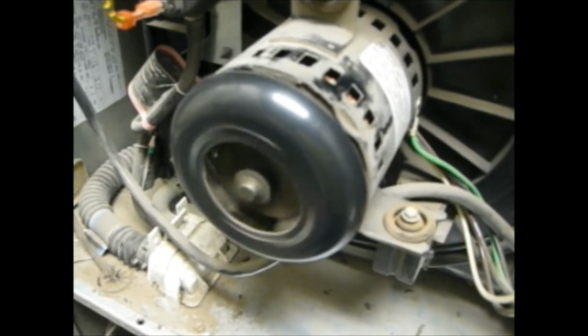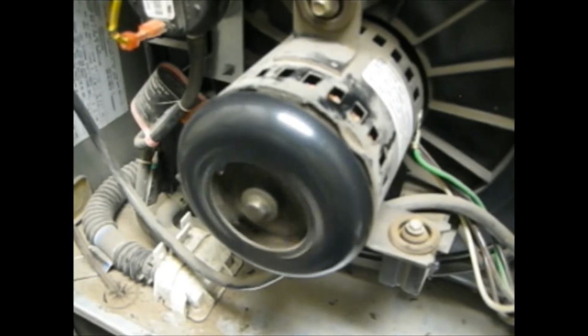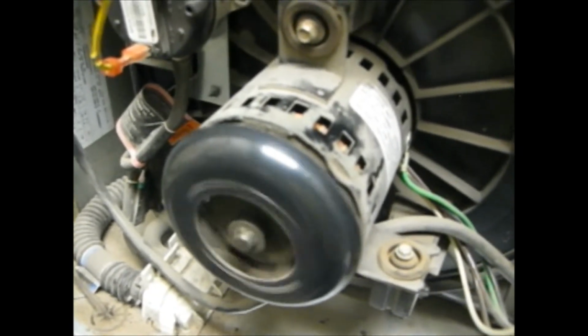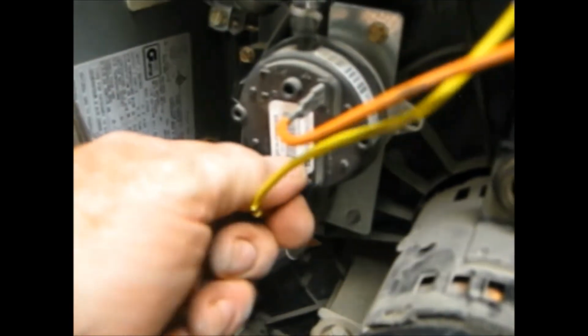If your inducer motor runs but you fail to get a flame in your combustion area, the next thing to test is your pressure switch, and these are quite easy to test. You will need an ohm meter.